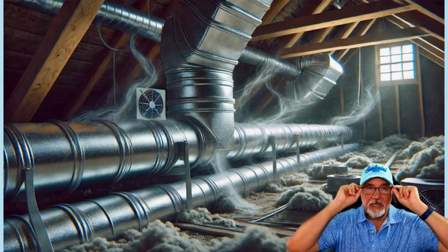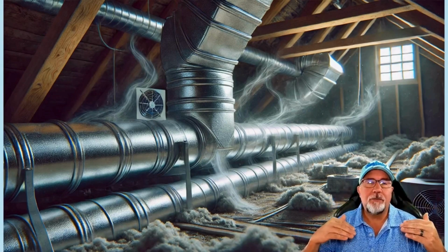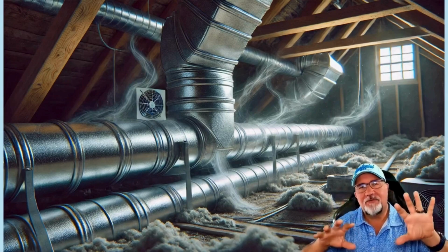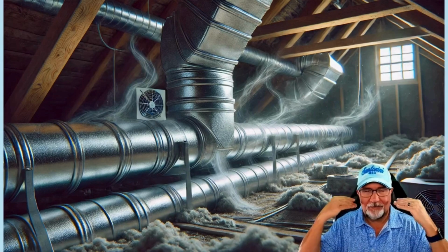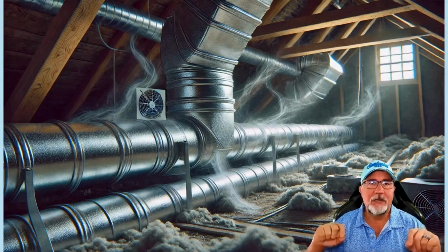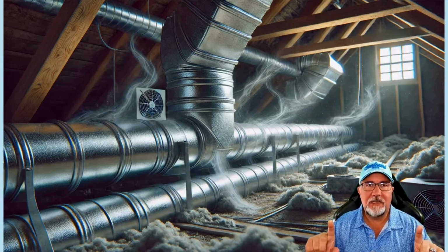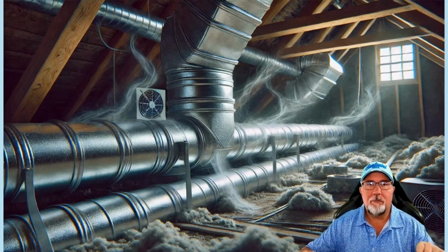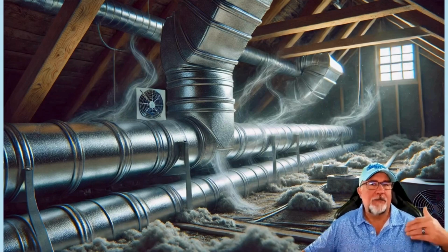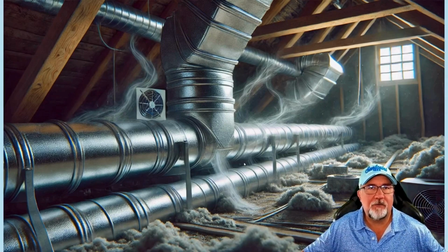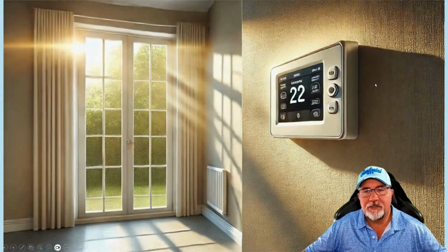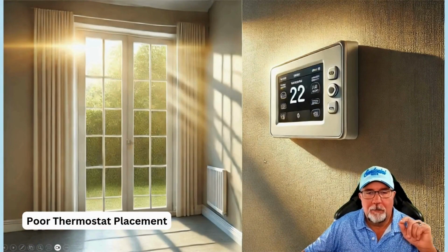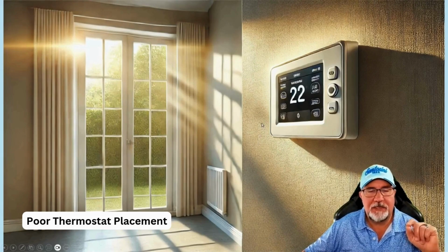But the key is the code calls for them to be between 48 and 60 inches. Now, usually about 54 to 55 inches is kind of a standard thing that we would tell our installers. But here's the key to making sure that the thermostat is in the right place. Okay, now we're talking about the thermostat and the placement. Let's go back to one of our pictures and let's show them. Okay, so here is a thermostat on a wall, but here's something that has to be considered.